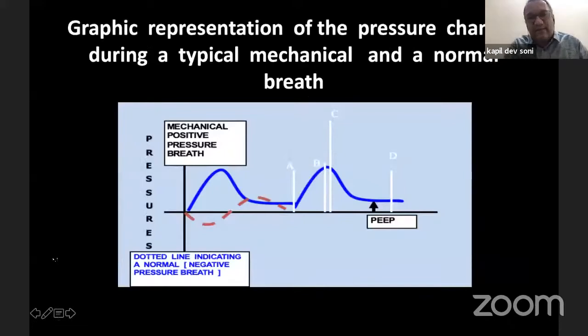A typical breath, if the patient is spontaneously breathing or a mechanical ventilator is giving the breath, how does it change? Pressure changes within the lung. So in this you can see what a normal spontaneous breath looks like. Initially there's a negative pressure generation, and then there is a positive pressure breath. So this is a natural breath. On the other hand, a mechanical ventilator is giving a positive breath. It starts with a positive rise in the pressures, then it reaches a plateau, and again it remains above the baseline if there's an addition of PEEP, and then comes the next breath.